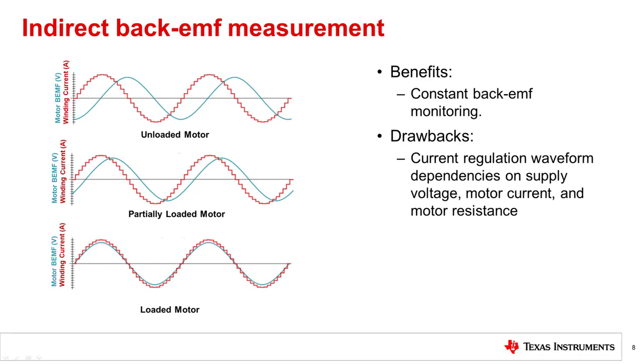However, a drawback of this solution is that the current regulation waveform can have heavy dependencies on supply voltage, motor current, and motor resistance, which can make it difficult to properly monitor the back EMF. The following slides will show how TI implements this solution for its stall detection algorithm and how it overcomes these drawbacks.